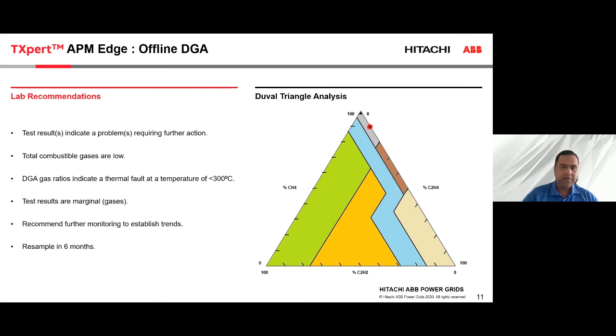So once you get that test report, we do not know what is the risk of operating that transformer. We do not know what has caused the issue. We do not know how much time we have before maintenance or what may be the reason. So what we did, we asked the end user to give us the data. Not only that data, we asked him to give us the DGA data for as many years as it was available. So we got data from 2016, 17, 18, and 19.